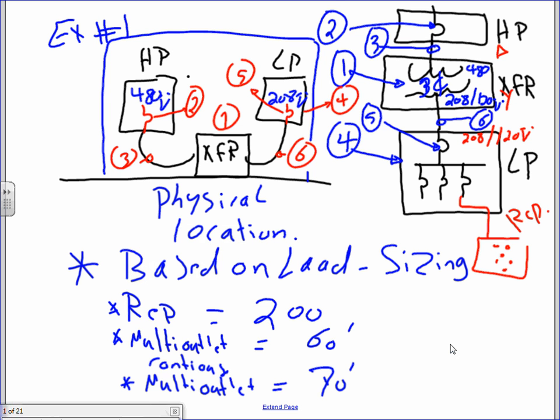High voltage, typically delta. We have a delta-wye transformer, 480 on the primary, and on the secondary 208/120. It's always three-phase, always three-phase. And then it brings a feeder into a panel. Here's my panel. The panel has a main, and you have multiple branch circuits. And from the branch circuits, we feed our receptacle circuits.